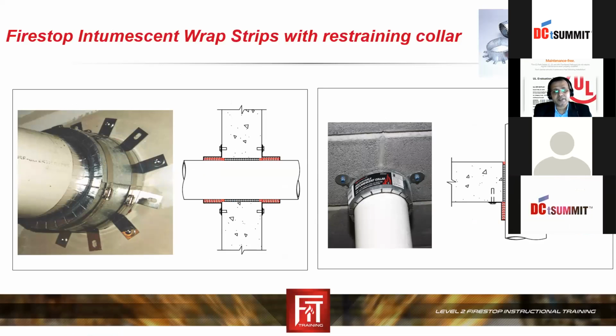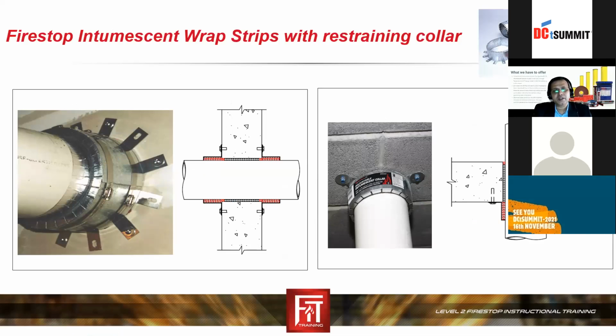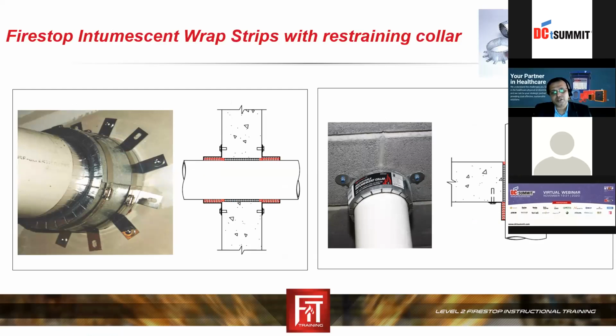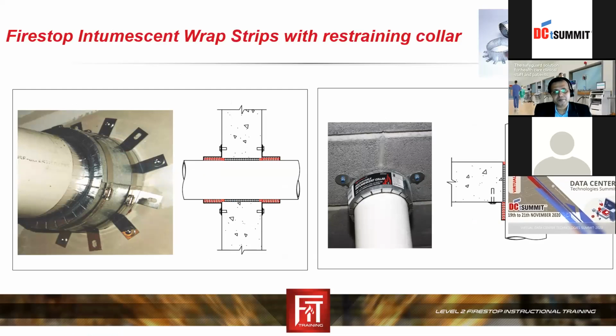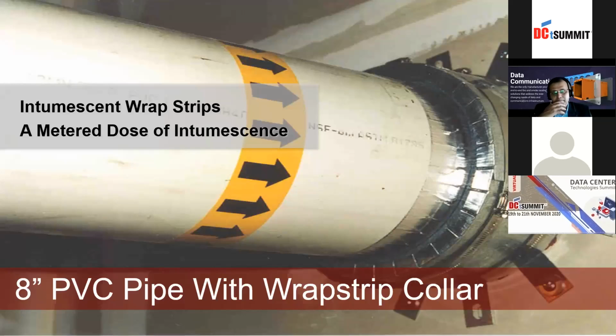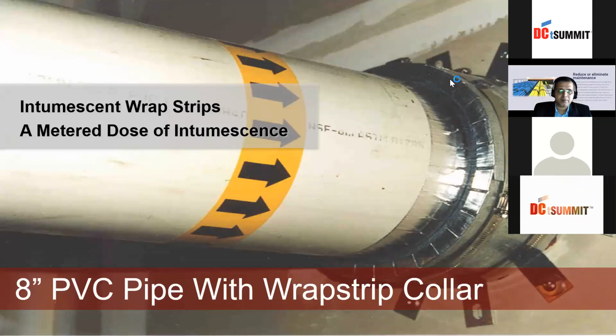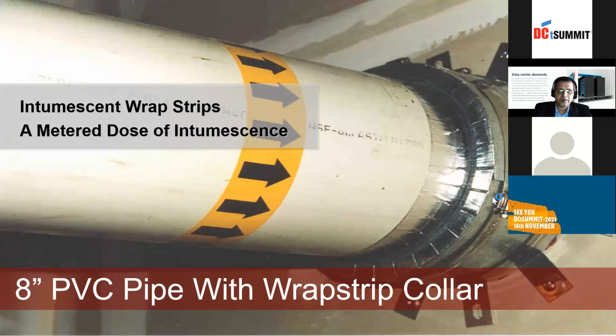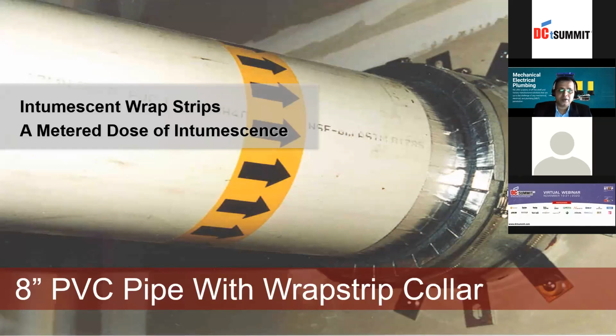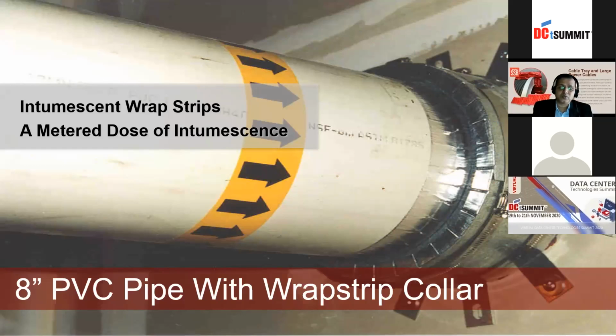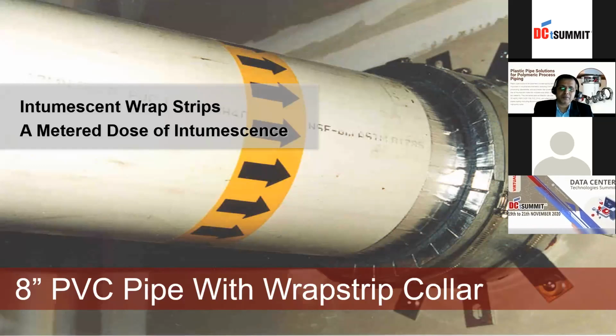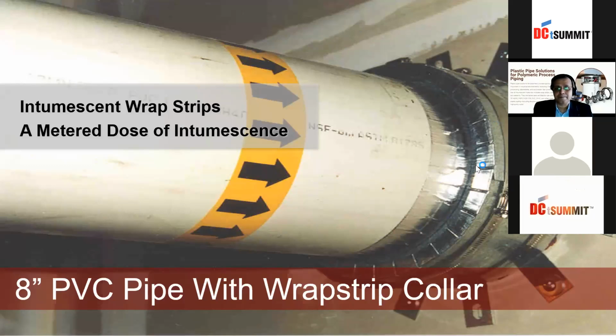The reason is that as the diameter of the pipe increases, a sealant will not suffice. The collar has more expansion power. That is the reason a collar is used for a 4, 8, and 10-inch pipe. Here you can see an 8-inch pipe. You can see the amount of wrap strip installed inside this, because that is the amount of intumescent product installed. That much expansion is required to close an 8-inch PVC pipe in case of fire.